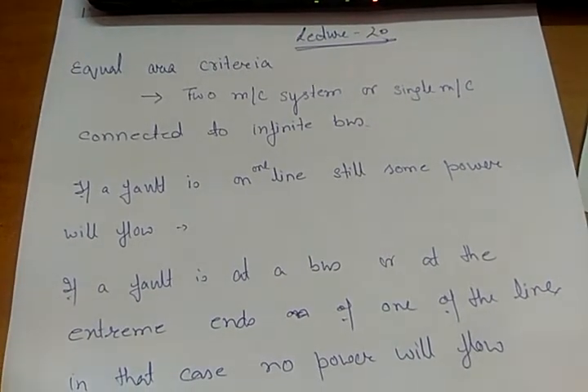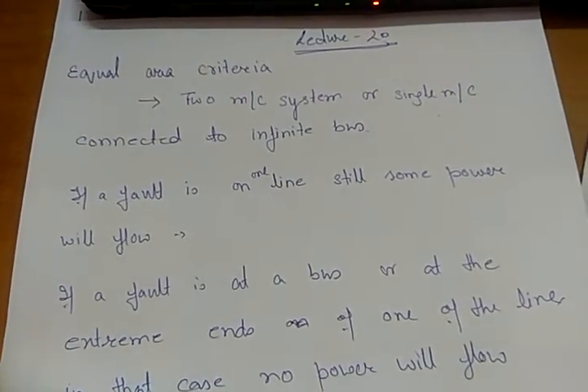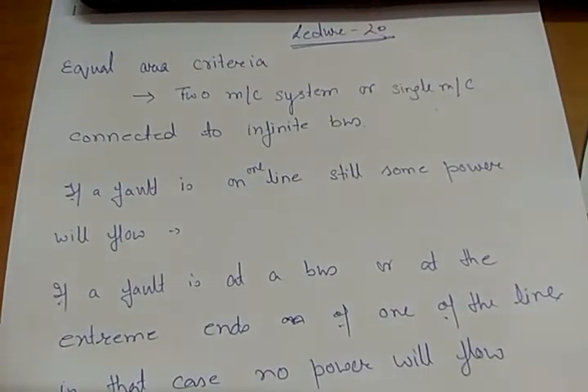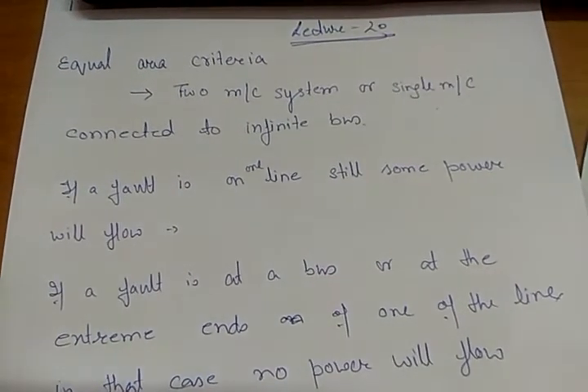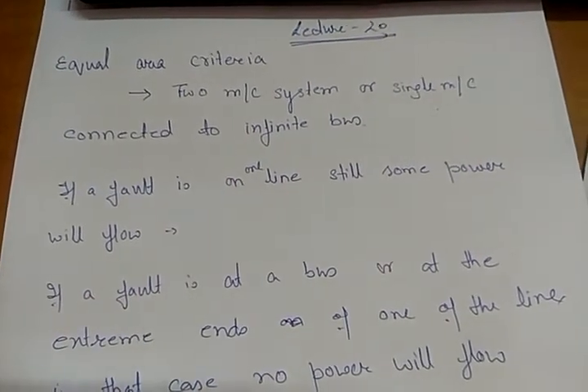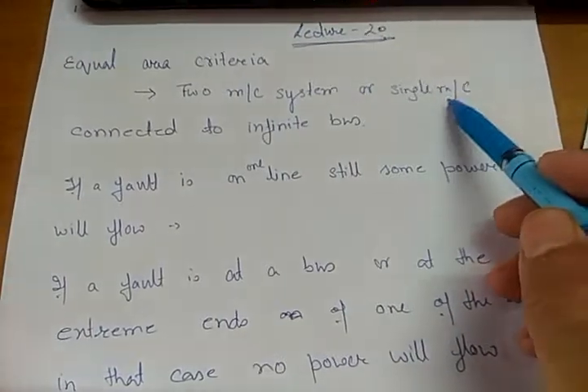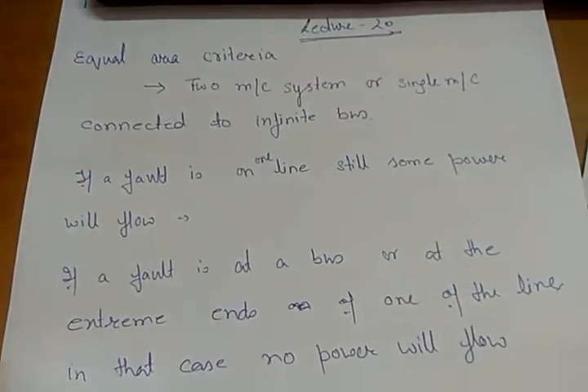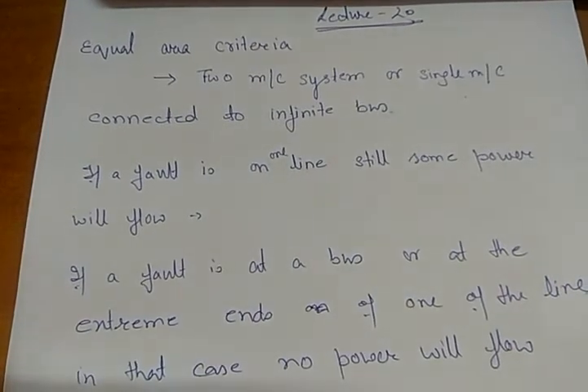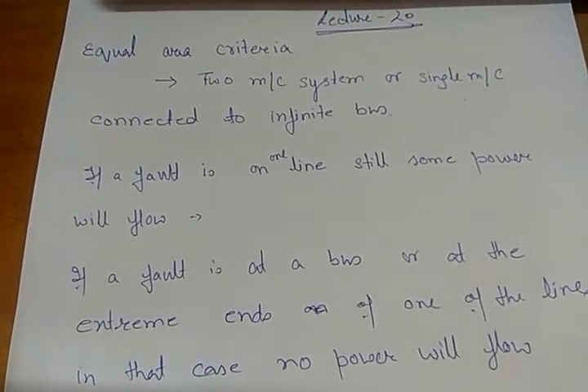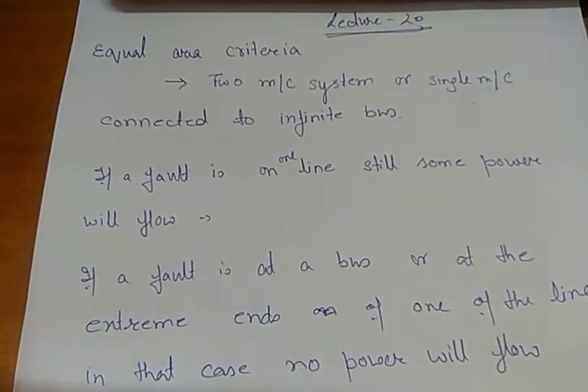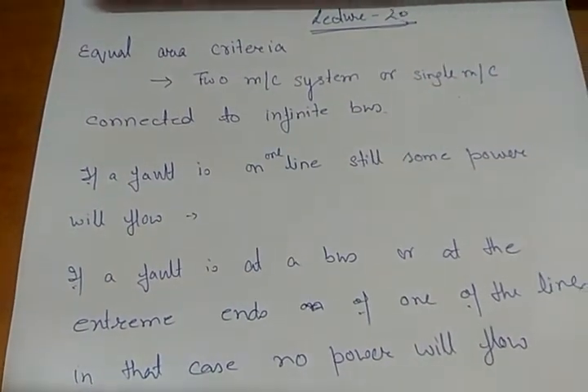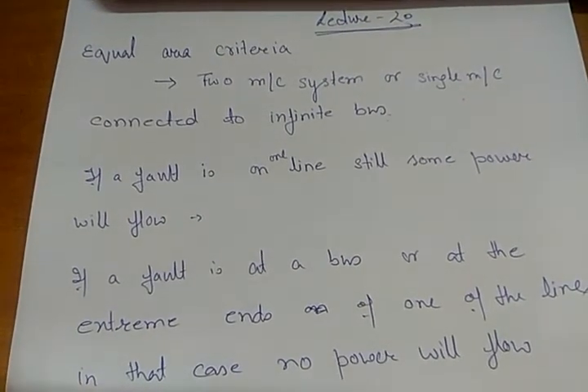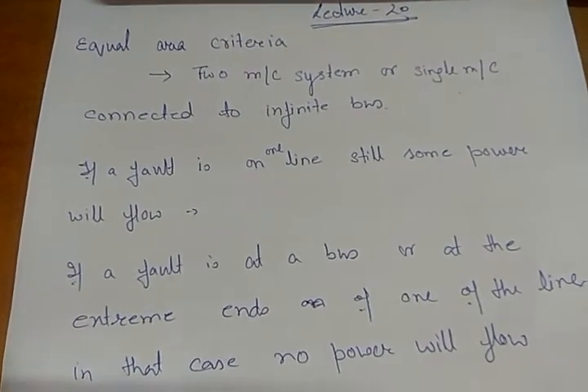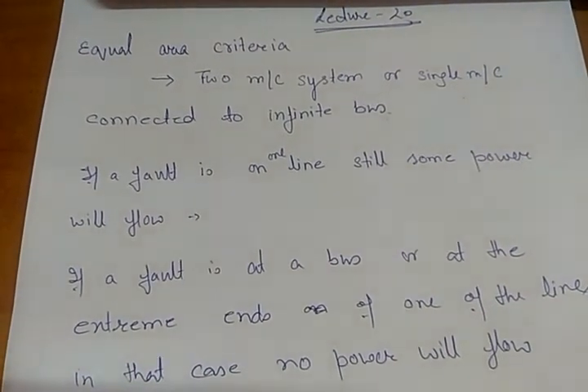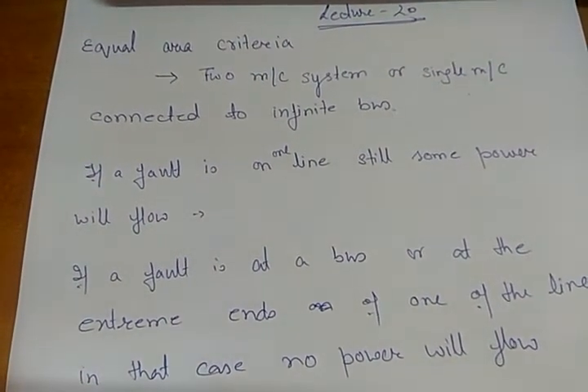But this equal area criteria has a limitation: it is applicable for analyzing the stability of a two machine system only, or a single machine connected to an infinite bus. If the complexity of the system increases, say I have 10, 50 or 100 generators, the mathematical computation will be very complex. There this equal area criteria cannot be applied.